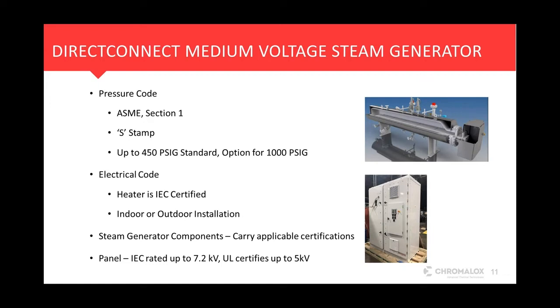So from a steam generation side, again, all the same standards apply with our Direct Connect series. ASME Section 1 is followed. We have the S-stamp. Traditional pressures are up to 450 PSI, but of course we can do custom designs even higher. And then the international standards that certify the heater to IEC, as well as the panel up to 7.2 kV and UL up to 5 kV, are all in place. And then, of course, the other components are really just what you would see out in the industry today in the low voltage systems. Between your valves and fittings, the sensors, and control components, those all carry the same certifications you would expect to see.